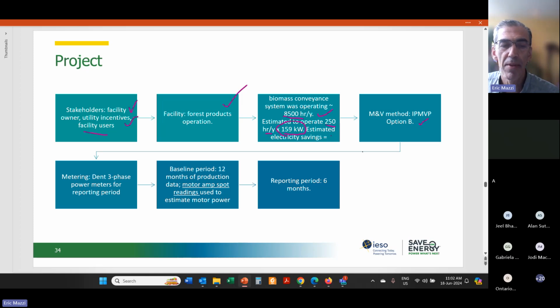It was again chosen to do an option B method. We used, again, DENT 3-phase power meters. So the baseline data, it was another situation where we had 12 months of production, but we only had motor amps or motor current spot readings for the baseline. So there was no 12 months of power measurements for the motor in the baseline for those 8,500 hours per year. It was just motor current, not real power, not kW, but motor amps that was measured. And then it ran a reporting period of 6 months because that was enough and it wasn't seen as particularly sensitive to the variables like outdoor temperature.